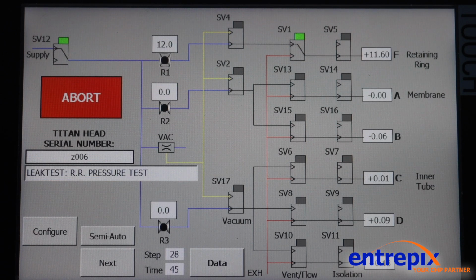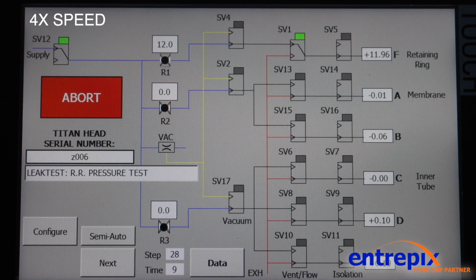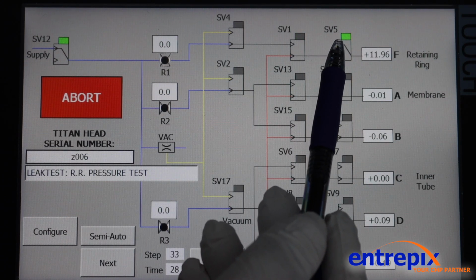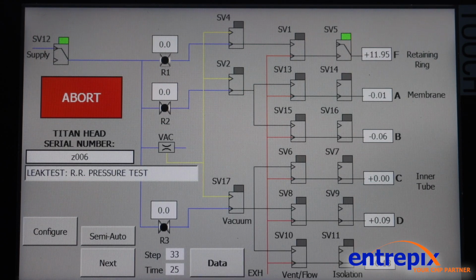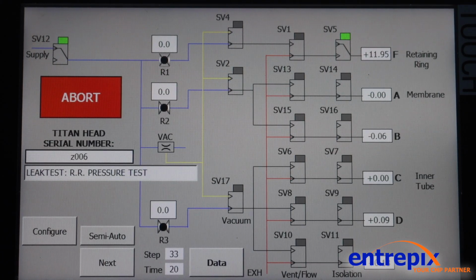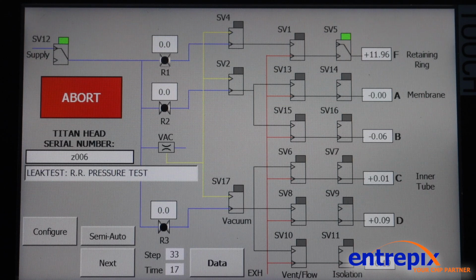As you can see, the tester is inflating the retaining ring to approximately 12 psi. Once this pressure is sensed as stable, it will seal or isolate the zone for delta pressure test leak over 30 seconds, as configured in the previous screen. Once the final valve is indicated as activated, it is isolated. It is now that the machine looks for delta over the 30 seconds. This process will repeat for the other remaining zones of the head.